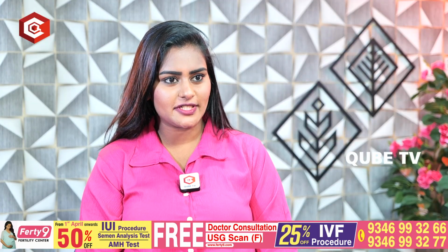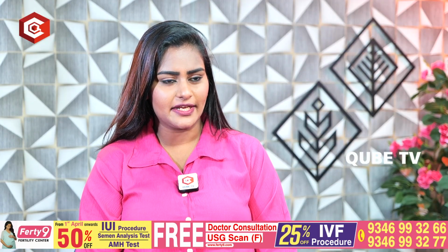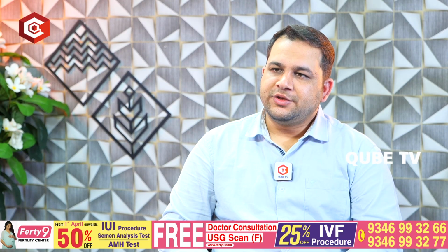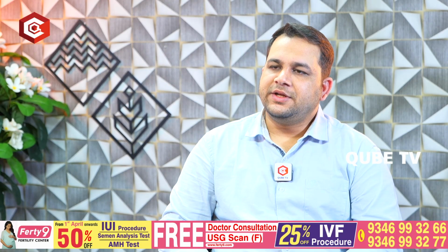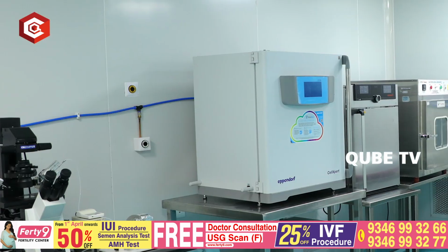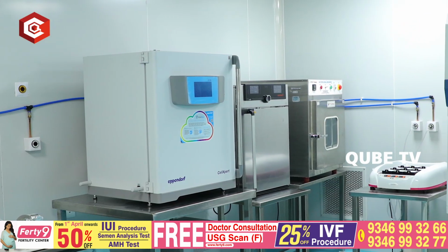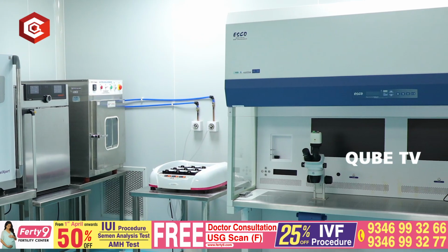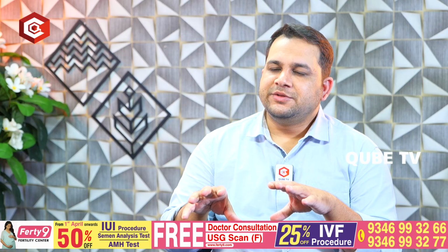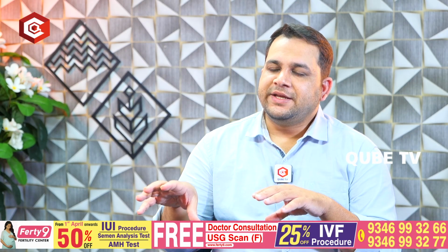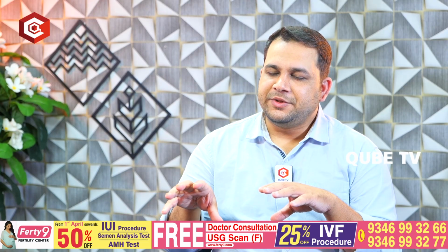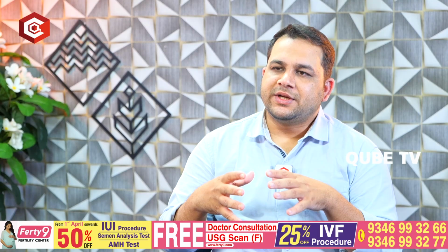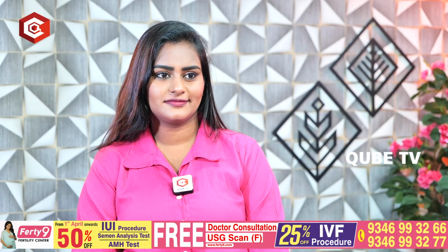So what are the different types of incubators available and how are they used, sir? Two types of incubator are there, one is the box incubator, one is the benchtop incubator. The box incubator is used only as a CO2 incubator. The other one is the benchtop incubator, where we use the K system, the Minc incubator. In that there are separate chambers, and we culture one patient per chamber only.